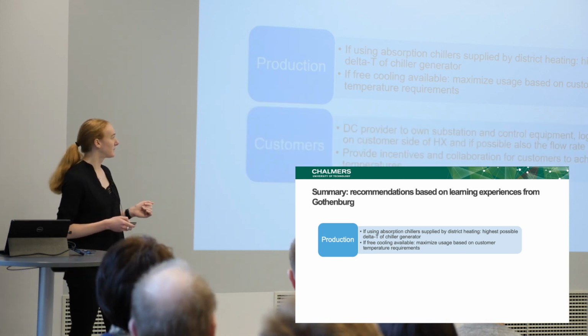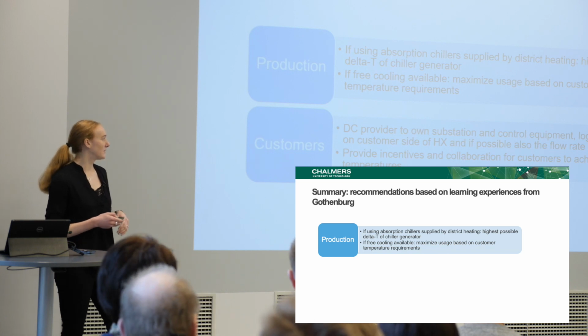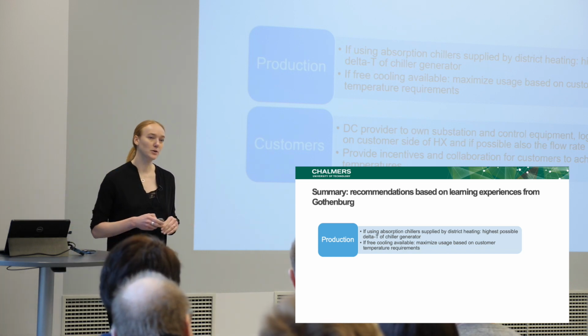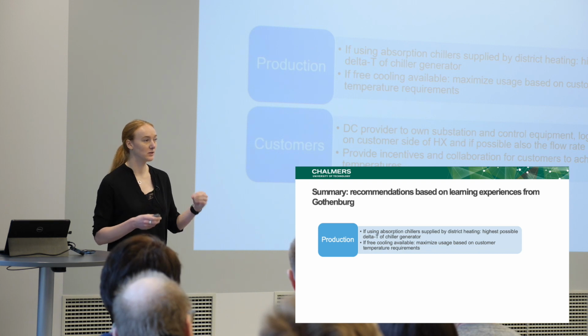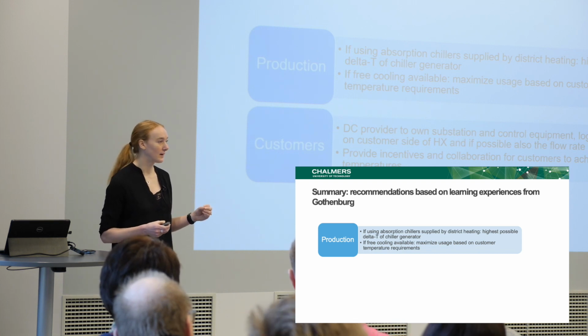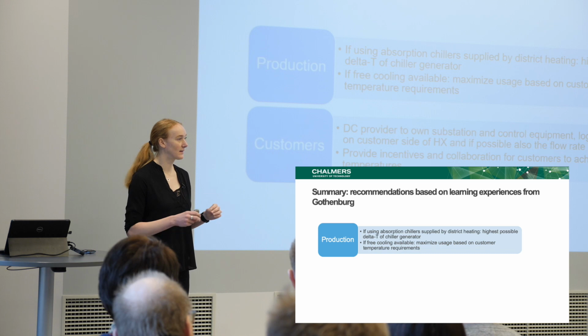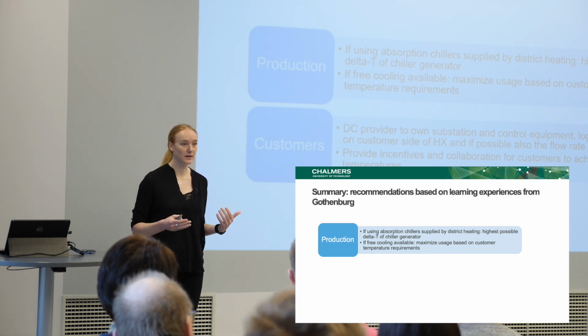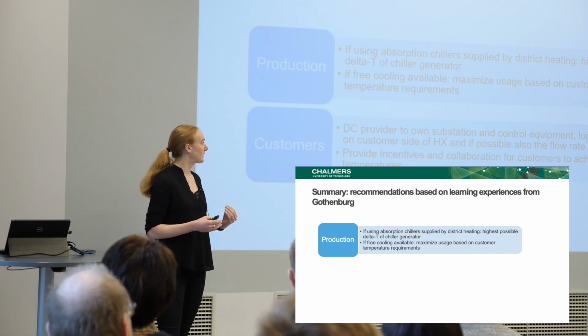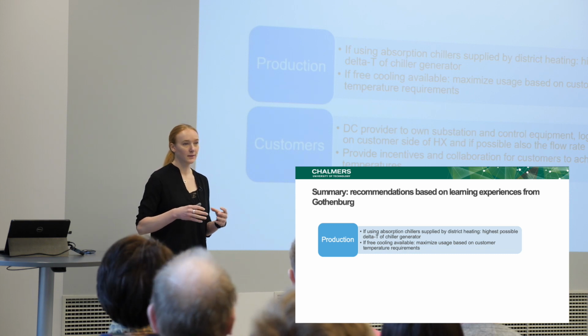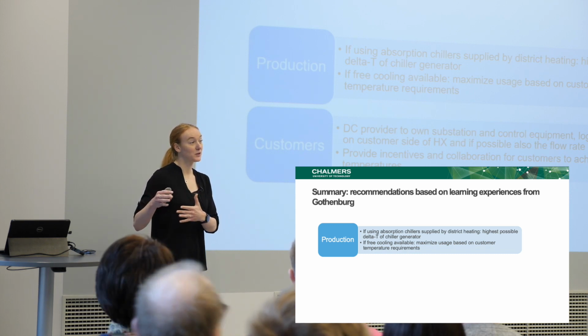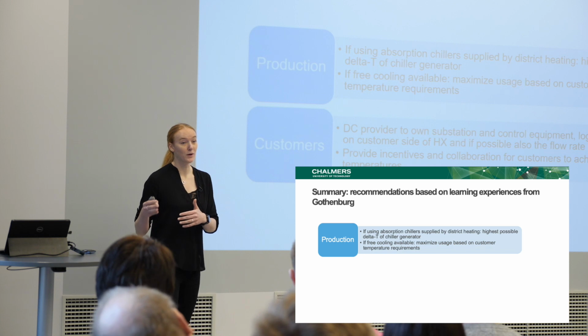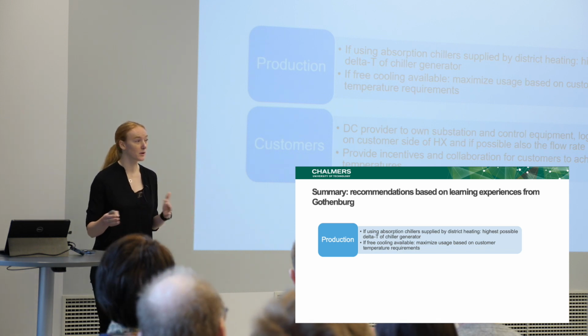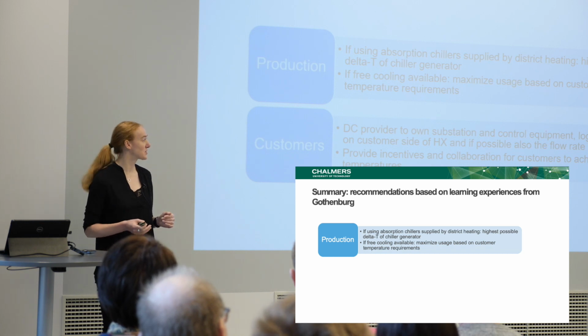And on the customer side, it's good if the district cooling provider actually owns the substation and all the control equipment of the district cooling customers, because it gives more control to see what actually happens. It's good if the building owners log their temperatures, but it's good if the district cooling provider also knows what these temperatures are, so there's more data and information communication between the two sides.